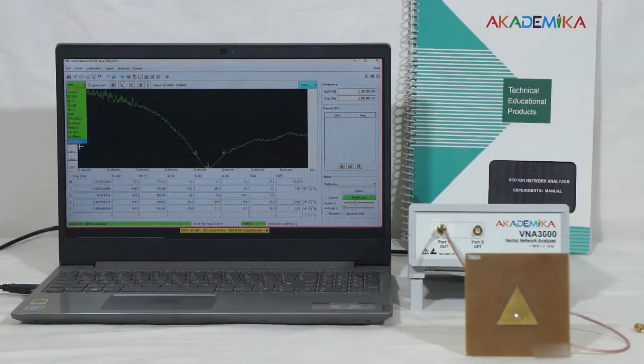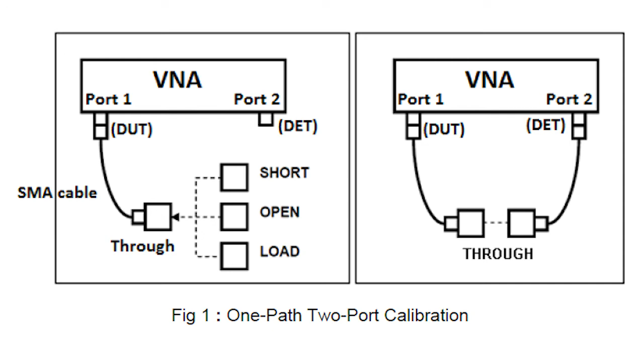Calibration of VNA. In this, we introduce the students to calibration of vector network analyzer. One-path, two-port calibration is used for measurements of the device under test parameters in one direction, for example, S11 and S21. This method involves connection of the three calibration standards to port 1 and connection of a through standard between port 1 and port 2.